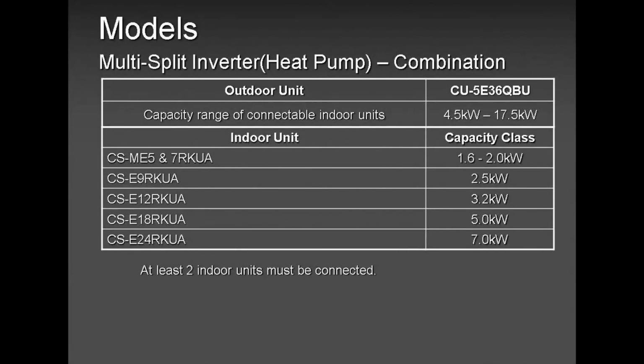Now this topic is going to talk about 5 zones, but the same thing applies to 2, 3, and 4 zones. Why do I say it's a 5 zone? Because you see 5, that stands for 5 zones. That's our nomenclature. CU stands for the outdoor unit. 5 stands for the zone. E stands for the series. 36 stands for the BTU, 36,000 BTU. Our four zone is 24,000. Our 3 zone is 19,000, and our 2 zone is 18,000.